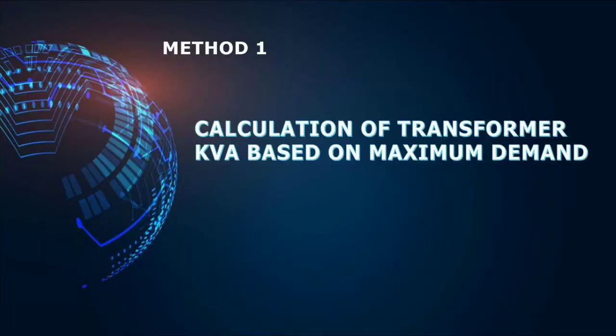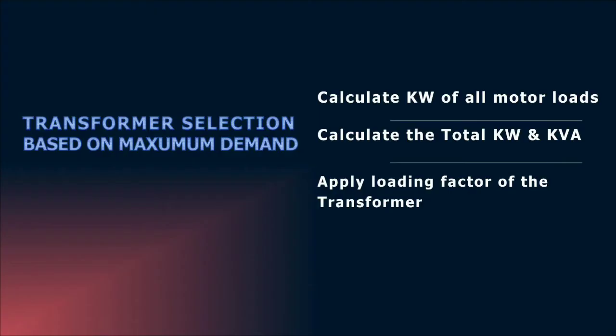Coming to the first method, we are going to select the rating of the transformer using the maximum demand of the system. Now we are going to see the steps involved in this method. In this method, we are calculating the kilowatt of all the motor loads, and from that kilowatt, we will be calculating the total kilowatt of the system. With the total kilowatt of the system, we can find out the kVA rating of the transformer required by applying the percentage loading of the transformer.